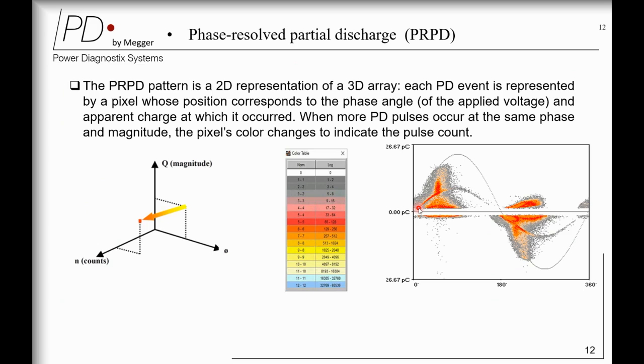So when I talk about conventional and non-conventional measurements, we are always interested in measuring PRPD, phase resolved partial discharge patterns. On the left hand side is my asset, and the right hand side is my PRPD pattern, which helps me identify what type of PD I have in my asset. So what is PRPD? It is a 2D representation of a 3D array. Each pulse event is represented by a pixel in this pixel table, whose position corresponds to its phase shift.